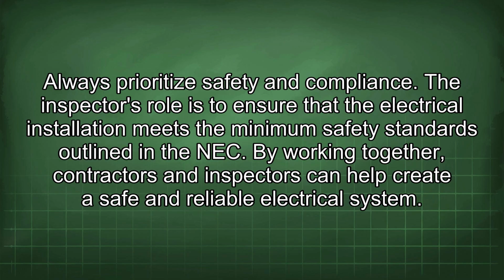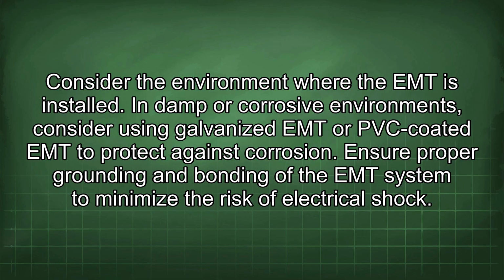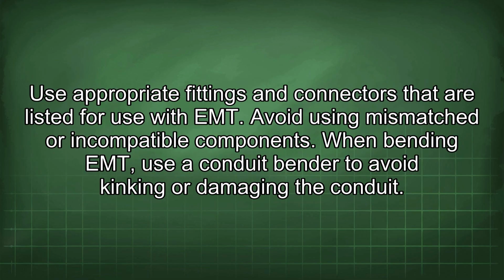The inspector's role is to ensure that the electrical installation meets the minimum safety standards outlined in the NEC. By working together, contractors and inspectors can help create a safe and reliable electrical system. Consider the environment where the EMT is installed. In damp or corrosive environments, consider using galvanized EMT or PVC-coated EMT to protect against corrosion. Ensure proper grounding and bonding of the EMT system to minimize the risk of electrical shock. Use appropriate fittings and connectors that are listed for use with EMT.